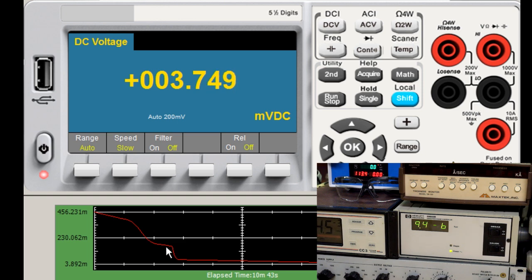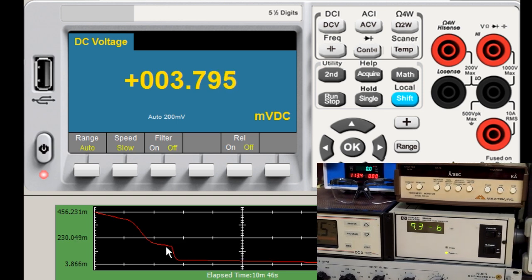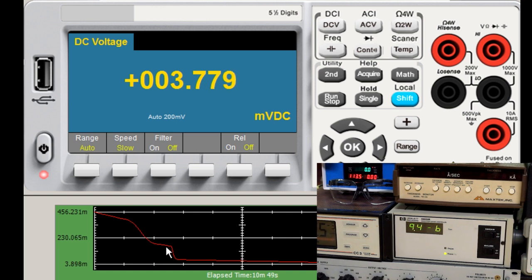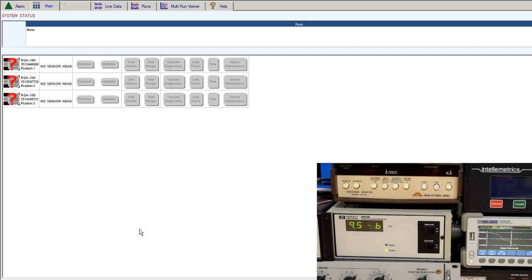You'll notice the first turbo should have been able to take it down all the way, so we're going to troubleshoot that problem in this video. I already know what it is and have a pretty good suspicion, but I'm going to show you how to use the RGA to troubleshoot that issue. We'll head over to the RGA software. You'll notice the pressure's still a little bit high — with these two turbo pumps, or even just one of these turbos, we should have no problem getting into 1×10⁻⁶ after just a couple minutes of pumping, and after a little bakeout, minus 7 or minus 8 should not be far away. There's obviously something going on here.